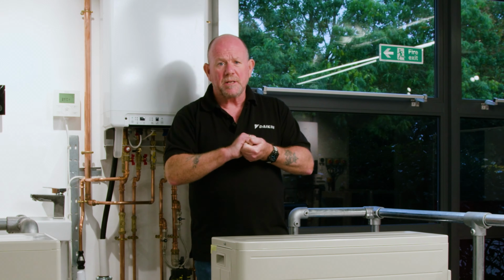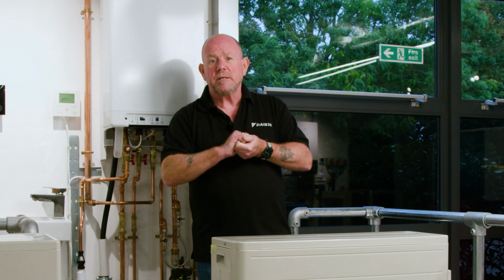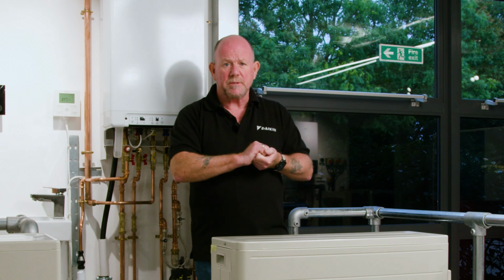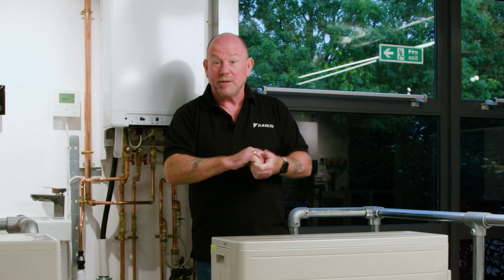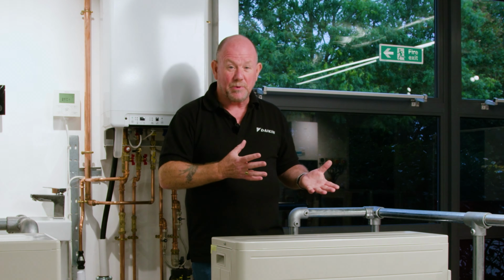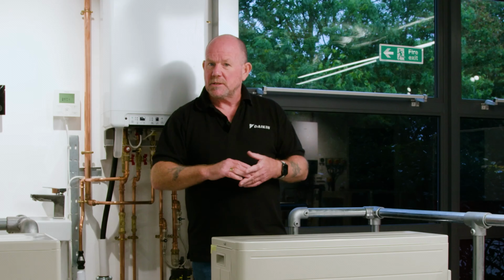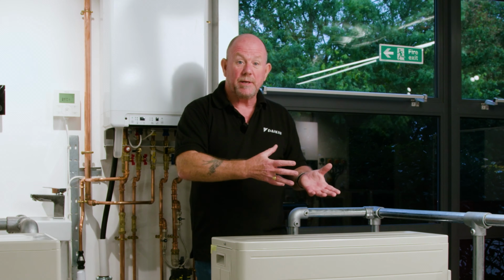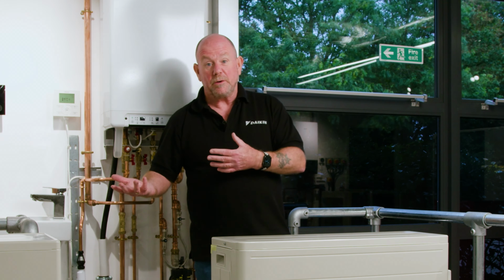BS 7593, which is the British standard for water quality in domestic heating systems, is now closely entwined with Part L of the building regulations. When you notify the installation of your heat generator, you are indeed stating that you have complied with the British standard as far as system water quality is concerned. Now the good news is this is no more onerous than it is for a gas boiler. All it's asking us to do is to ensure that our system's clean. So in other words, we've cleaned the system with a chemical cleaner post-installation. It's asking us to ensure that we've correctly dosed the system with inhibitor and biocide if required. So no more onerous than when you install a gas boiler, an LPG boiler, or indeed an oil boiler.